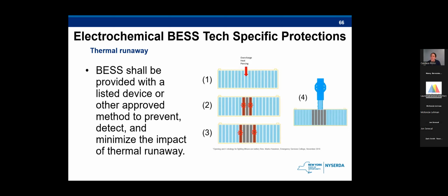So you have that overcharge, maybe heat or piercing in step 1. Step 2, that one cell is going, affecting the cells next to it. And then 3, it's continuing to propagate a bit. And in this image, it shows that in 4, they're putting water on those specific cells. That could just be the battery management system instead of putting water specifically on those cells, as that's a bit difficult. Could just be isolating that entire module from the rest of the system to ensure that it doesn't propagate.